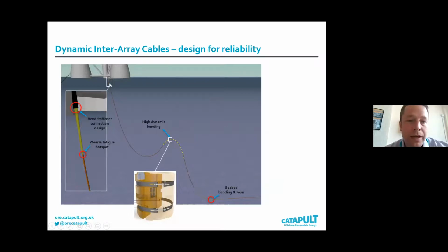And then the other thing that you look at, which tends to cause failure, is two parts. One is the top of the bend stiffener, where it connects into what's called a J tube, so it connects into the fixed platform or the fixed structure. That mechanism can often fail because of the way these are installed. Sometimes that isn't particularly robust. So that's one area that can fail. The other area is typically right at the tip of the bend stiffener, where the cable is moving back and forwards, and that tends to cause some bending and abrasion, local wear issues there. So you can often see failures right at the edge of the bend stiffener.